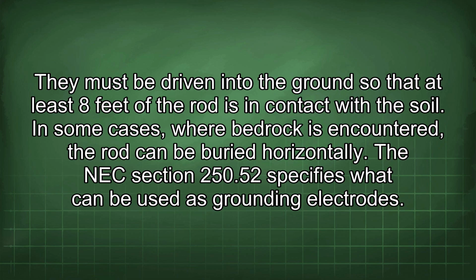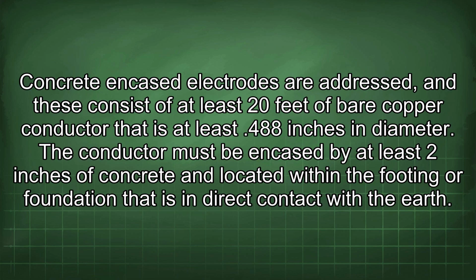The NEC section 250.52 specifies what can be used as grounding electrodes. Concrete encased electrodes are addressed, and these consist of at least 20 feet of bare copper conductor that is at least 4 AWG in diameter. The conductor must be encased by at least 2 inches of concrete and located within the footing or foundation that is in direct contact with the earth.